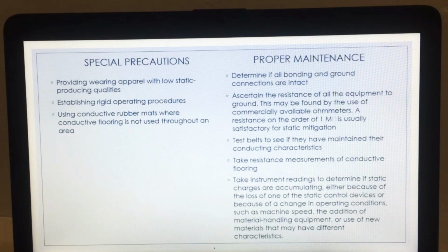Okay, for the special precautions: providing wearing apparel with low static producing qualities, establishing rigid operating procedures, using conductive rubber mats where conductive flooring is not used throughout an area, and lastly, proper maintenance. Determine if all bonding and grounding connections are intact. Ascertain the resistance of all equipment to ground. This may be found by the use of a commercially available ohmmeter. A resistance on the order of 1 megaohm is usually satisfactory for static mitigation.